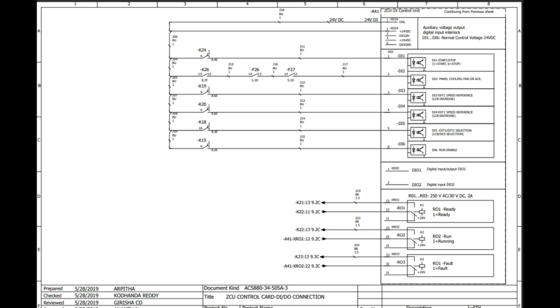Coming to the bottom part, there are different relays, RO1, RO2, RO3. The voltage rating is 250 volt AC, 30 volt DC, and 2 amps. In all three relays, there is an internal relay which will operate from 24 volt. Once the drive is internally healthy, that RO1 internal relay will actuate, and the signal coming and going will change state. Similarly, if the drive is running, the NO/NC change will happen internally, and similarly with fault.